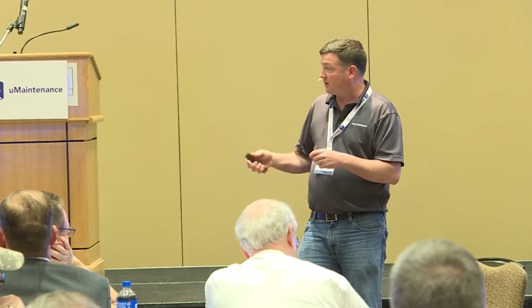So this is the way I kind of picture a Monitoring and Diagnostics Center. The M&D Center takes thousands of measurement points. All this feature data we're sending now into Pi—somebody creates a model. Inside Pi, all of the machines are set up with templates, so each machine template will have temperature points, pressure points, vibration points, and it's all set up as a template. Then you put it into this model, and the model will take all those templates and predict the value it should see for a data point.